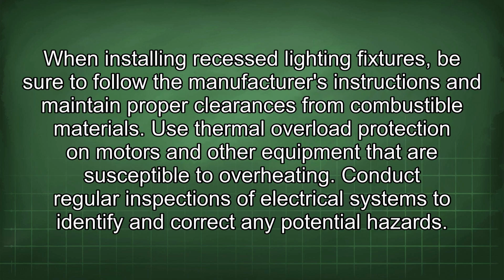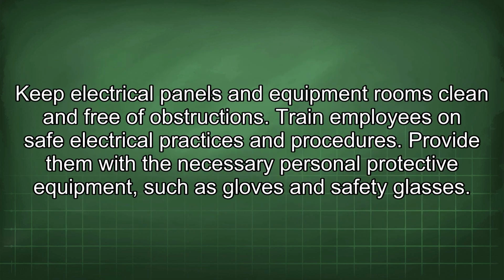When installing recessed lighting fixtures, be sure to follow the manufacturer's instructions and maintain proper clearances from combustible materials. Use thermal overload protection on motors and other equipment that are susceptible to overheating. Conduct regular inspections of electrical systems to identify and correct any potential hazards. Keep electrical panels and equipment rooms clean and free of obstructions.